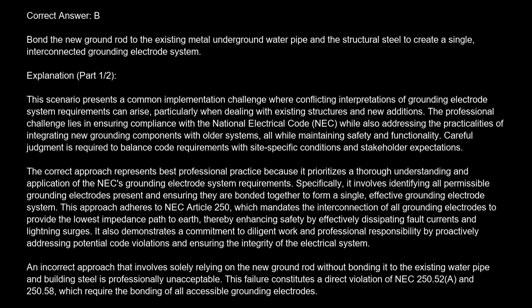This approach adheres to NEC Article 250, which mandates the interconnection of all grounding electrodes to provide the lowest impedance path to earth, thereby enhancing safety by effectively dissipating fault currents and lightning surges. It also demonstrates a commitment to diligent work and professional responsibility by proactively addressing potential code violations and ensuring the integrity of the electrical system. An incorrect approach that involves solely relying on the new ground rod without bonding it to the existing water pipe and building steel is professionally unacceptable.